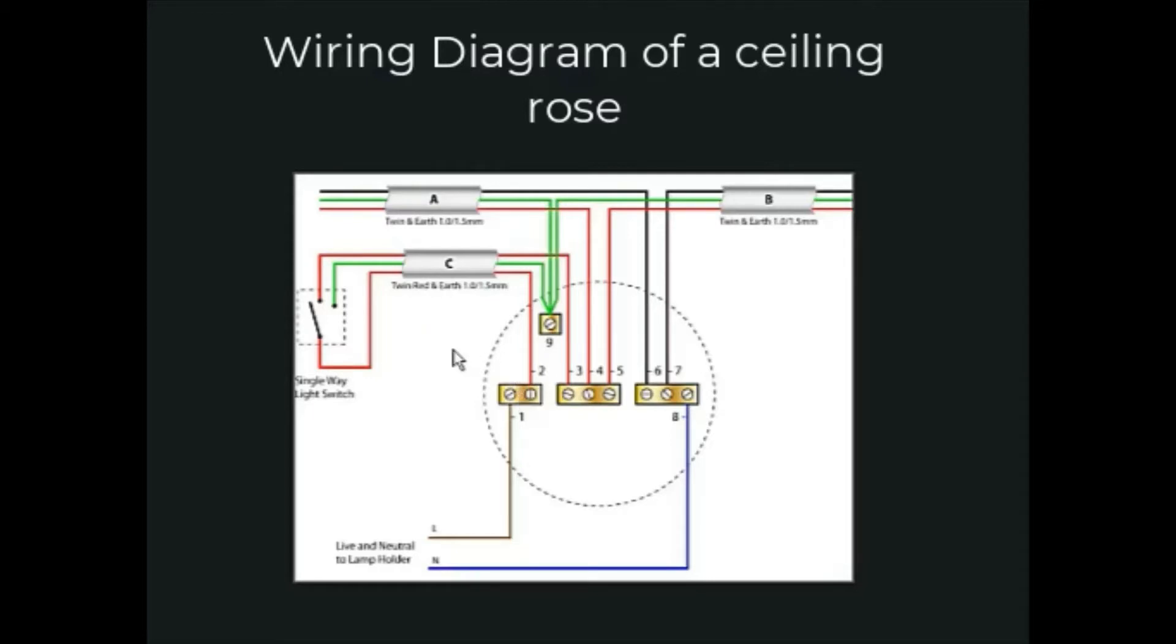Cable A loops into the ceiling rose from either the fuse board or another light. Cable B loops out of the ceiling rose to the next light fitting. Cable C is the switch live cable.